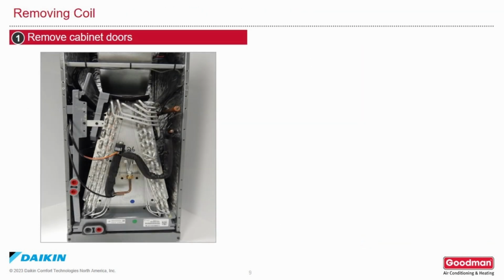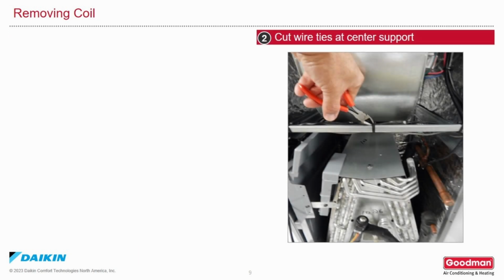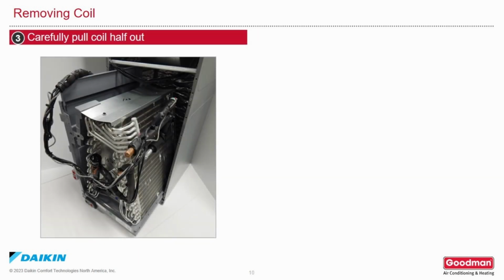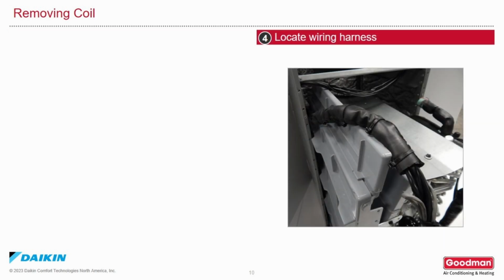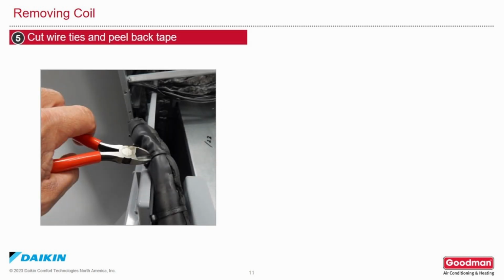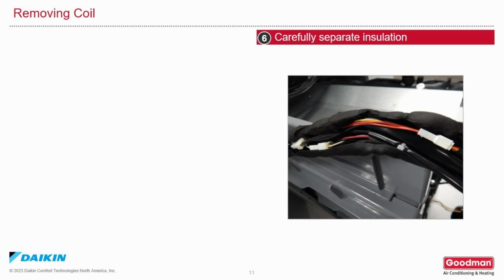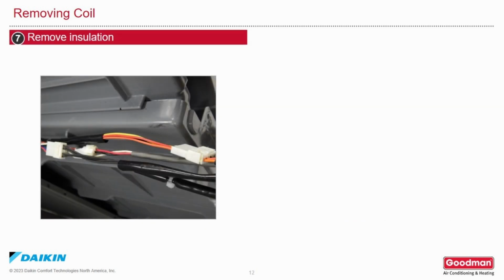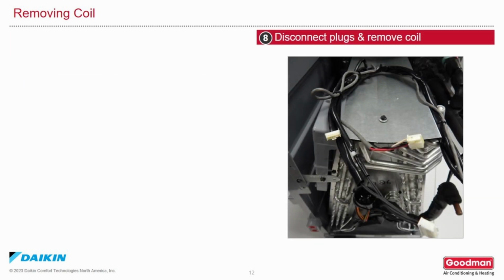Remove the cabinet doors and cut the wire ties at the center support. Then carefully pull the coil halfway out and locate the wiring harness. Then cut the wire ties and peel back the tape and carefully separate the insulation. Then remove the insulation, disconnect the plugs and remove the coil.